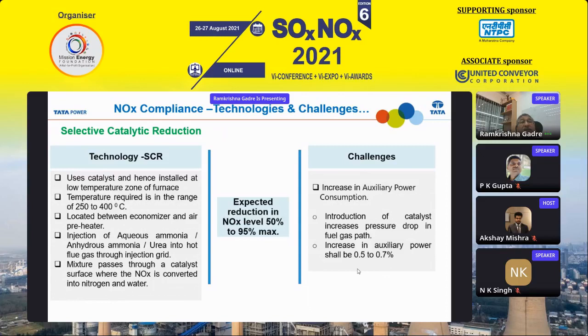The last technology is SCR, required for plants that have to meet the 100 mg per Nm3 norm. This requires a lot of modifications in the boiler, and becomes very difficult for retrofits. New plants can plan the catalyst tower along with the original design, but installing this catalyst tower into an existing plant makes the layout a big challenge, because you have to take a tapping before the air preheater, route the flue gases to this tower, and then put it back to the APH. This is a huge set of changes to the existing setup, and accommodating these things in the existing layout is going to be tough.